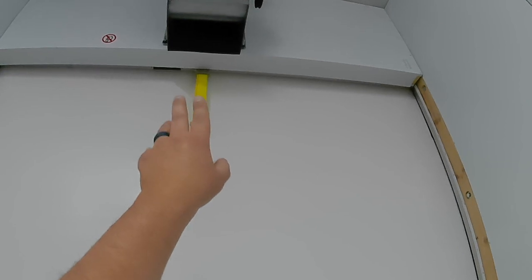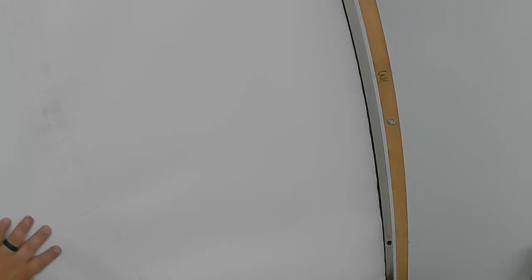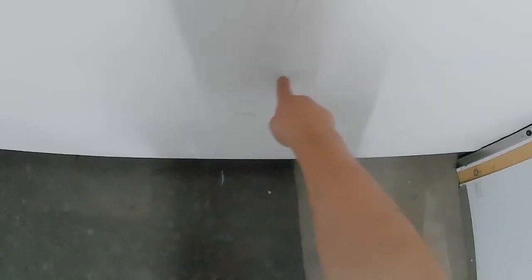Now what was happening is they have this blower hooked up right here, and when the door was fully closed, the blower was blowing, and this material right here in the middle was getting in and breaking the sensing beam between those two photo eyes, and that was throwing me way off the mark when it came to troubleshooting this thing, boys.